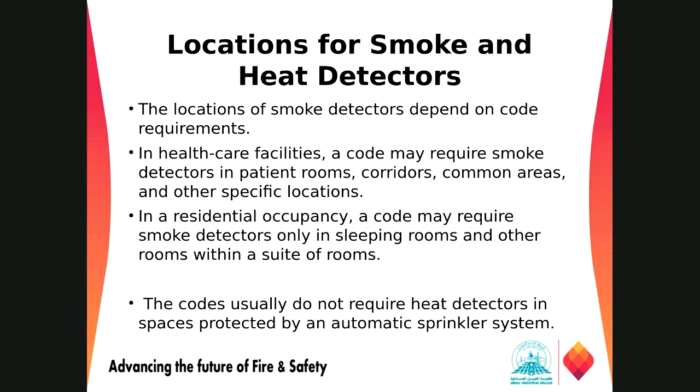Heat detectors we don't need in a building which is protected by an automatic sprinkler system. So if a building is protected by a sprinkler system, we don't need a heat detector, because the concern is that the fusible bulb will also work as a heat detector, right? So the bulb will fuse, water will start to flow, the fire will be extinguished, and the flow switch will give a signal to the fire alarm panel that there is something inside those areas.